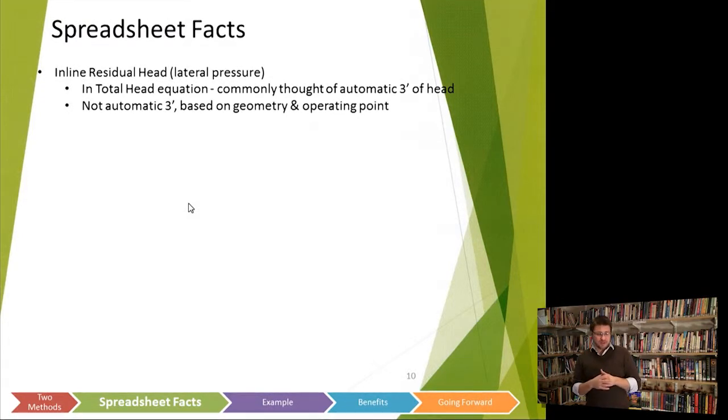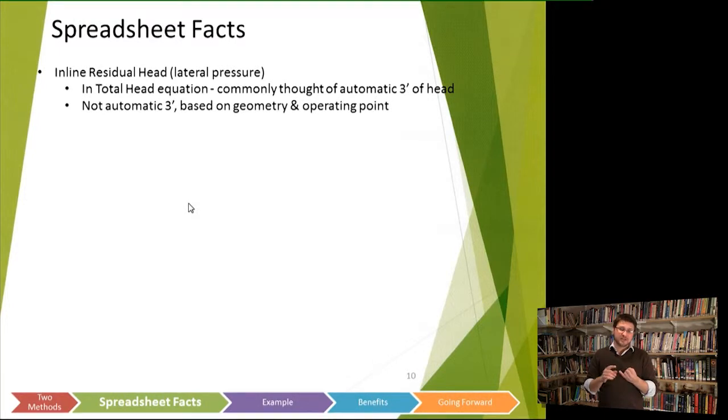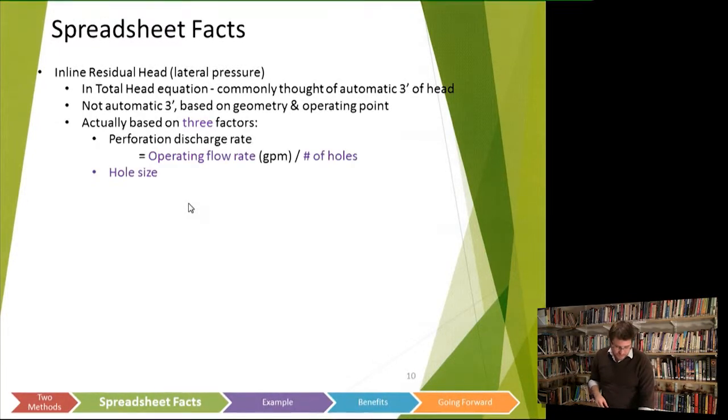Therefore, with these spreadsheets you don't enter the inline residual head as an input. It's actually an output of the spreadsheets. It tells you what the inline residual head is based on the number of holes that you have and the operating point. Okay, so this basically describes what I'm talking about here.